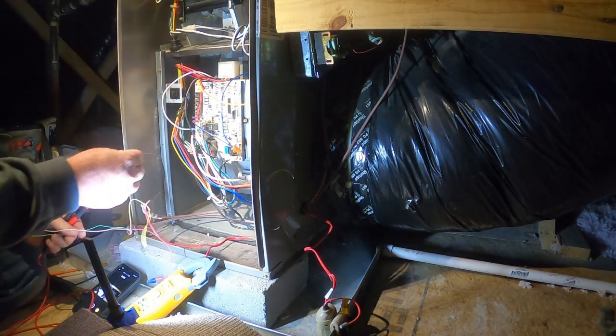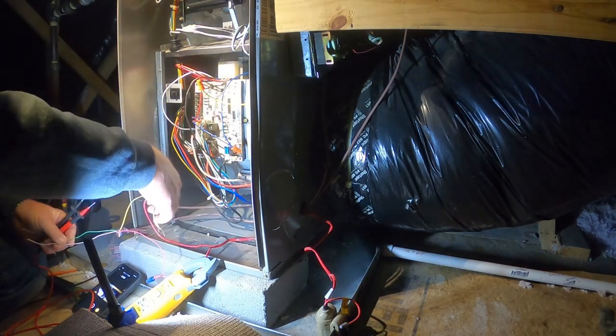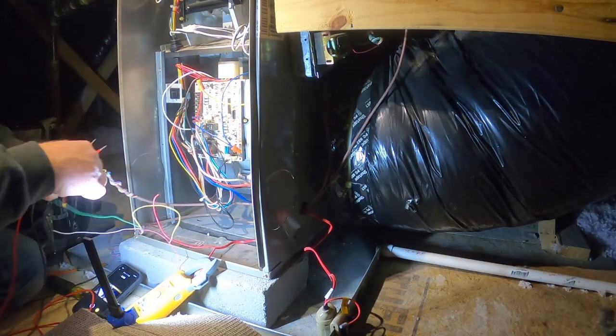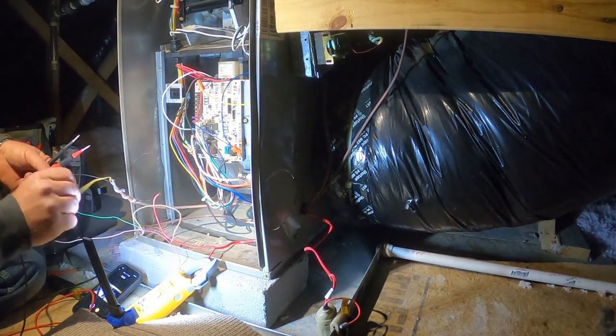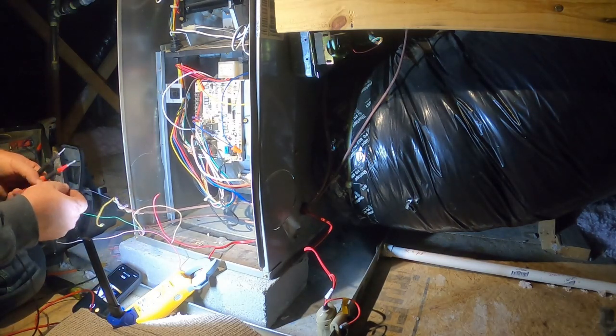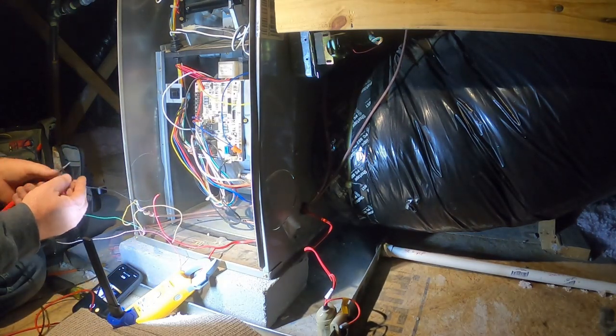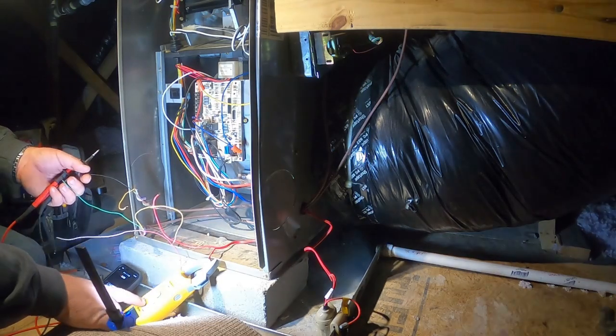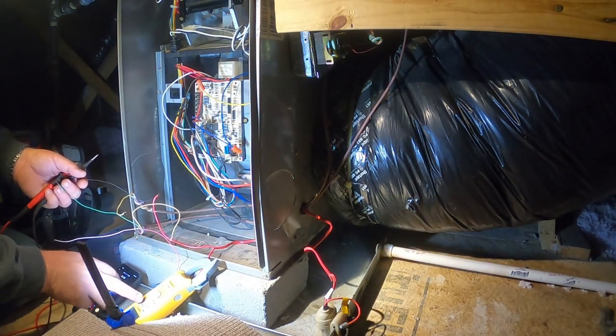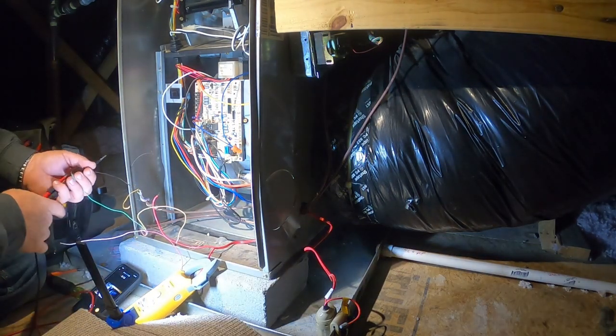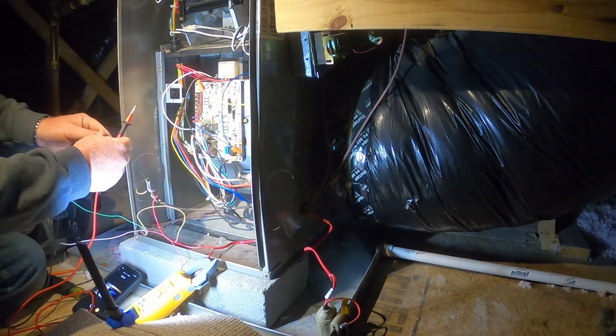So real quick, from up here, if that's a little cheap straight AC carrier out there, I should be able to go between common and Y and ohm out that coil. There may be a pressure switch in it, I don't know, may not. Let's set this thing and ohm it out real quick from up here.